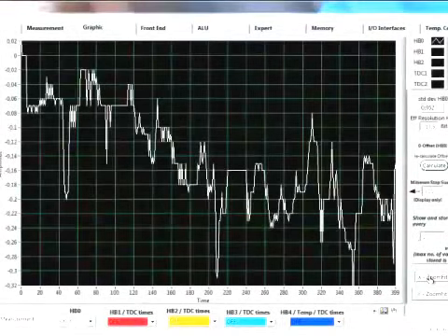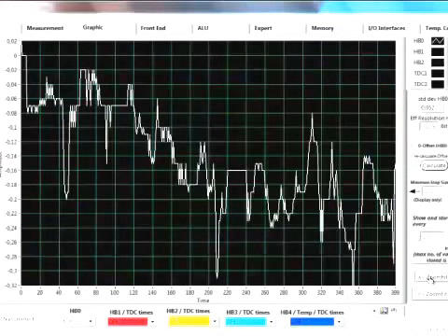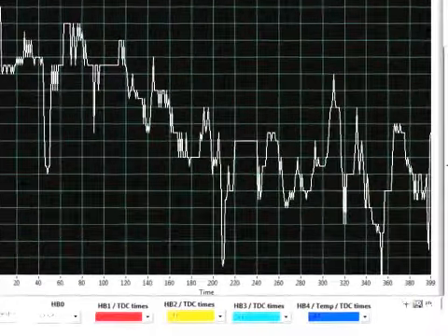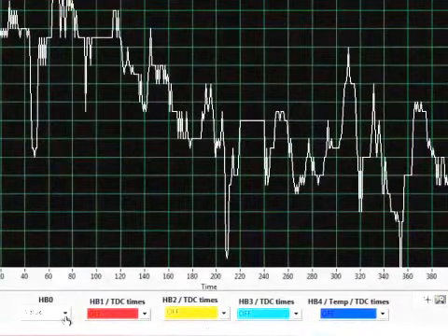Next, we will see the graphic sheet. As the name implies, this sheet displays all the measurement results graphically. Again, the individual half-bridge measurement results HB1 to 4, the consolidated measurement result HB0, and the temperature measurement result can be displayed here on the sheet. You can select which result ought to be displayed using the drop-down boxes here.